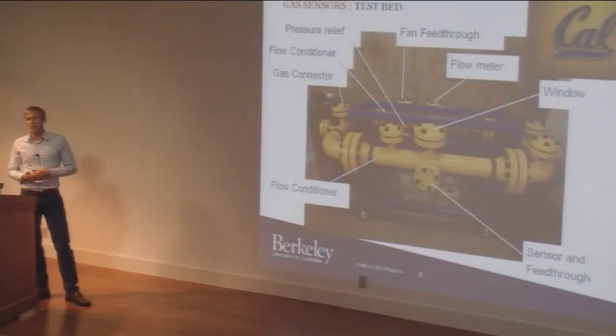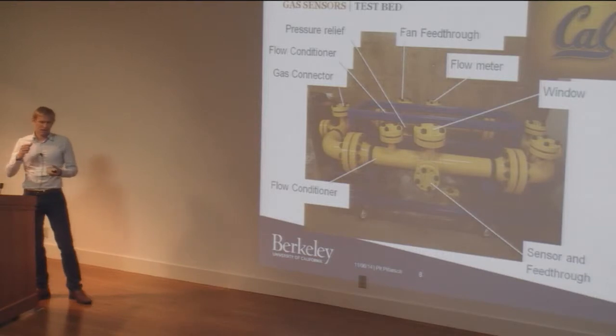General specifications: this is standing downstairs in this building, in the basement on campus. We are testing up to 200 psi in air for safety reasons. But it is certified — it has undergone X-ray testing, hydro testing, and everything to give the complete certification to actually use this test bed for methane up to 1350 psi. So we can get to very realistic conditions with this test bed once we move it off-site for safety reasons.